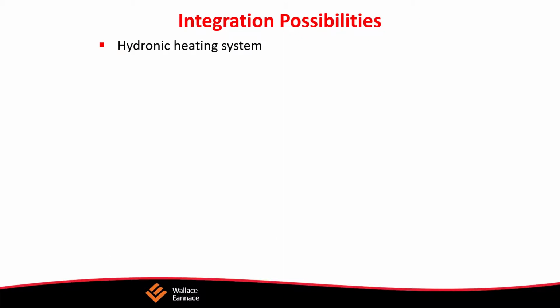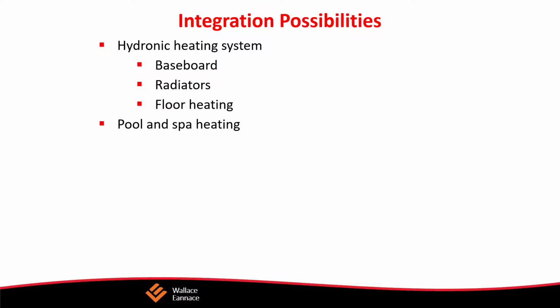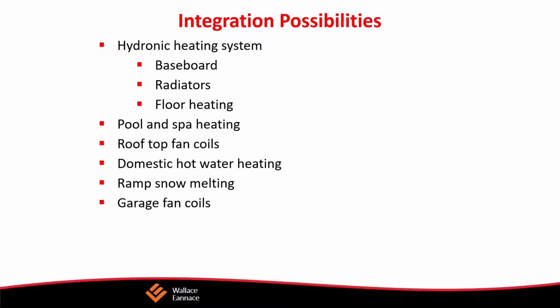Now, integration possibilities. Let's look first at our hydronic heating system. We have baseboard, radiators, or in-floor radiant heating. You may have pool and spa heating. You have fan coils, rooftop fan coils, providing heat for various coils. Domestic hot water heating is a big part. In many buildings, the domestic hot water load is much greater than the heating load. In a lot of cases, you need to design the system for providing domestic hot water, and you need to provide it without oversizing the regular hydronic heating system or space heating system.